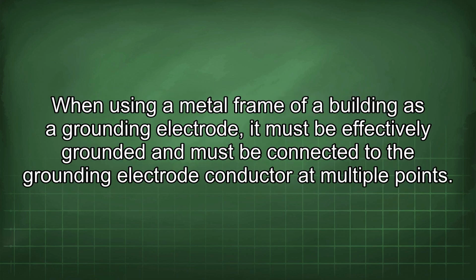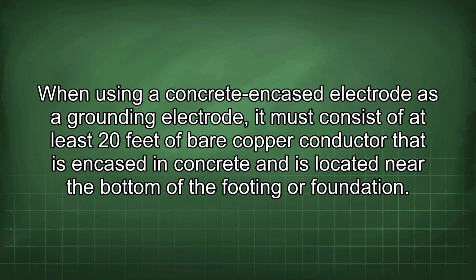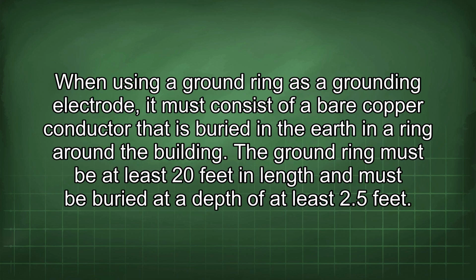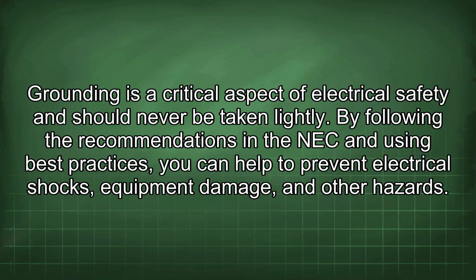When using a metal frame of a building as a grounding electrode, it must be effectively grounded and must be connected to the grounding electrode conductor at multiple points. When using a concrete encased electrode as a grounding electrode, it must consist of at least 20 feet of bare copper conductor that is encased in concrete and is located near the bottom of the footing or foundation. When using a ground ring as a grounding electrode, it must consist of a bare copper conductor that is buried in the earth in a ring around the building. The ground ring must be at least 20 feet in length and must be buried at a depth of at least 2.5 feet. Grounding is a critical aspect of electrical safety and should never be taken lightly.